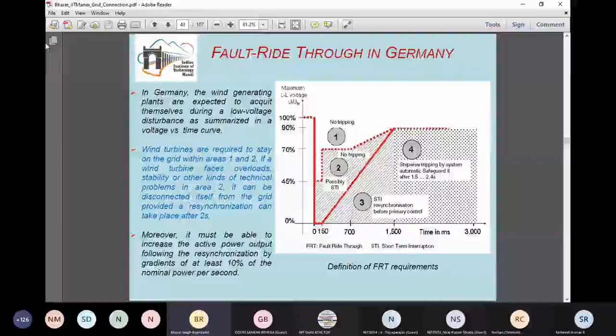It means the wind farm or wind turbine technology should be capable enough that if the grid has zero voltage where the wind turbine is connected, the system should not be disconnected. Earlier, what used to happen? Earlier, when the penetration level of wind energy conversion systems was very low, the wind turbines were simply disconnected, and during that abnormal condition, conventional synchronous machines used to supply the active and reactive power and maintain the system. But now it is expected that, as the penetration level of renewable energy goes beyond 20%, they can't be disconnected during such fault and abnormal conditions.